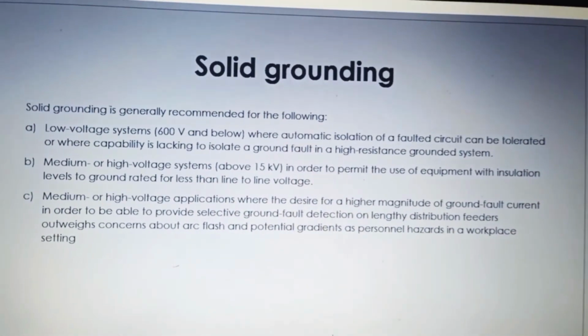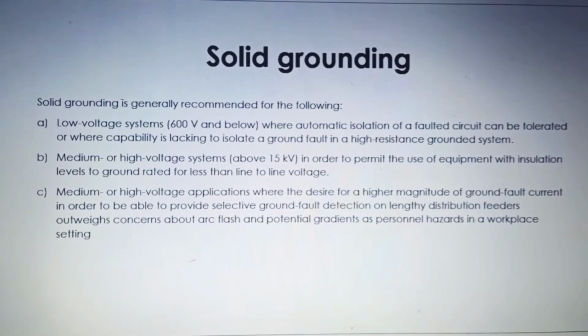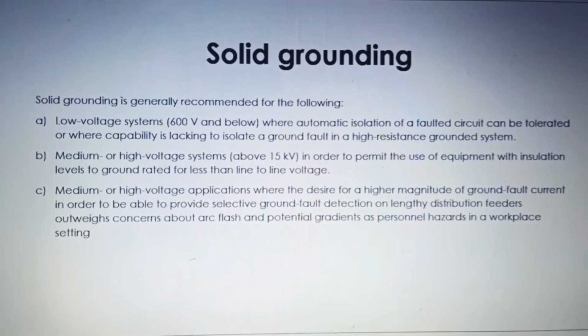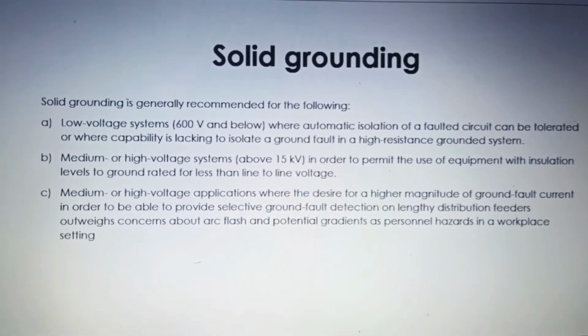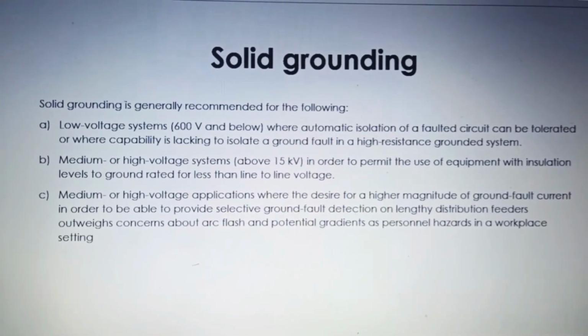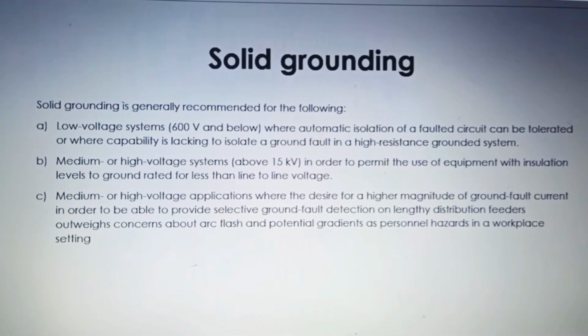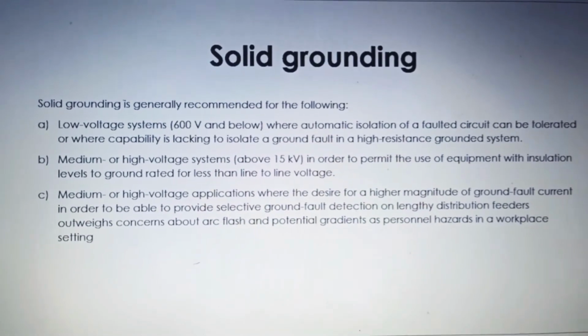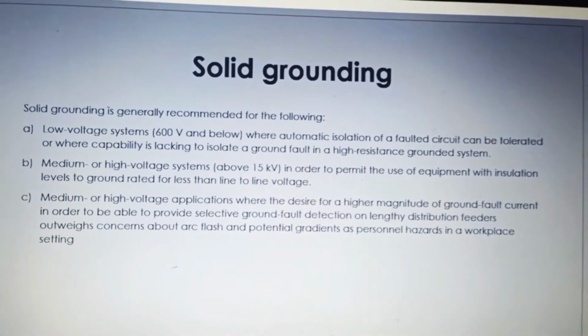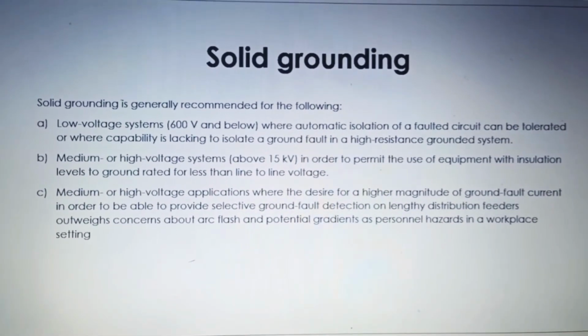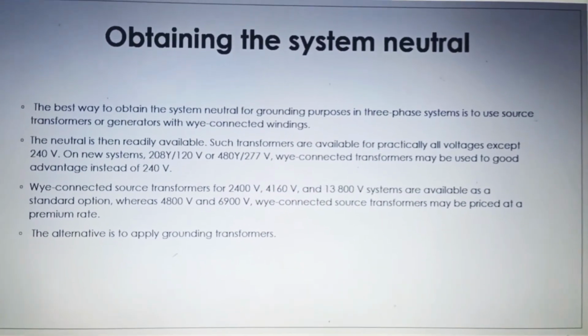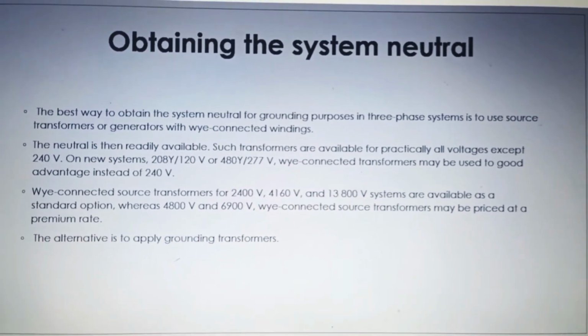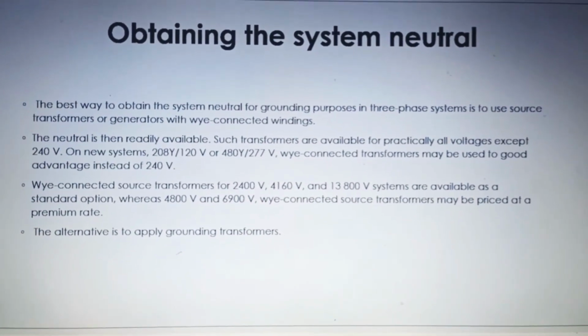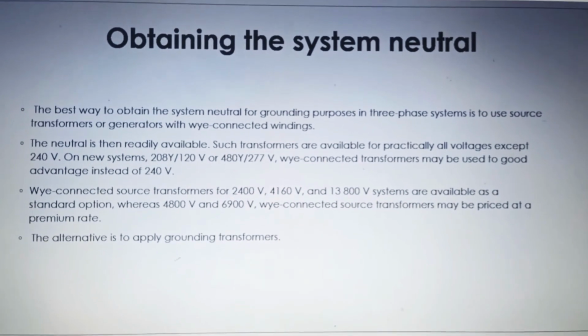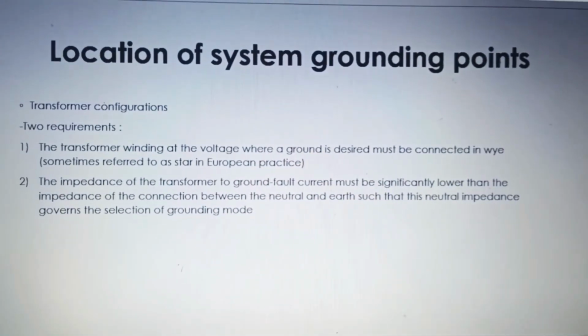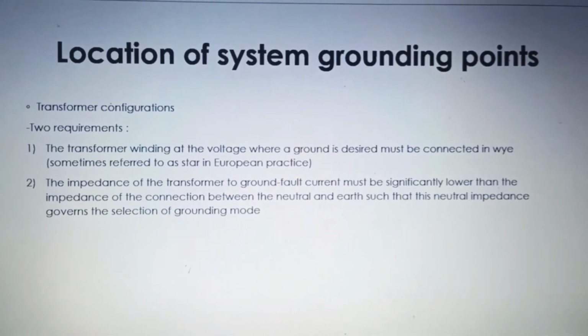And also, medium or high voltage applications where the desire for a higher magnitude of ground fault current, in order to be able to provide selective ground fault detection on lengthy distribution feeders, outweighs concern about arc flash and potential gradient as personnel hazard in a workplace setting. The best way to derive the system neutral for grounding purposes in a three-phase system is to use a source transformer or generator with Y connection. For the location of the system grounding point for a transformer, we need two requirements.